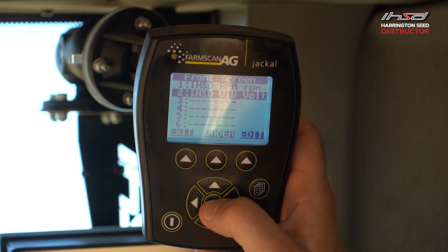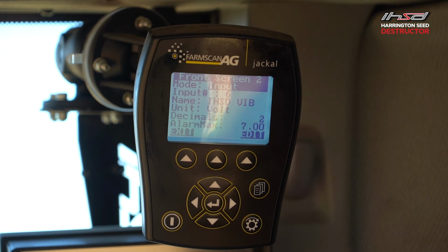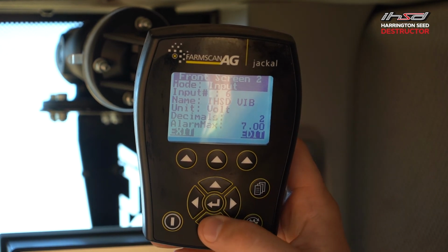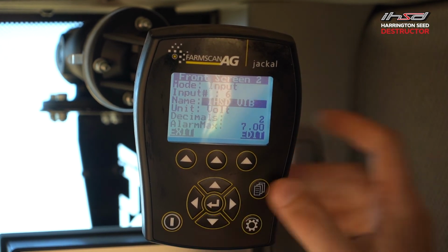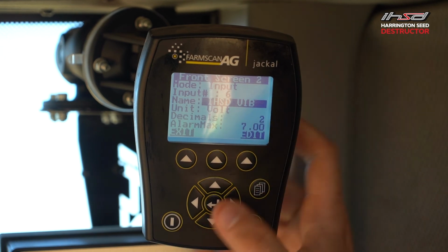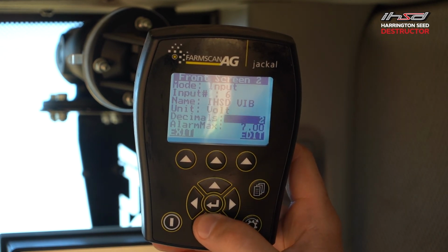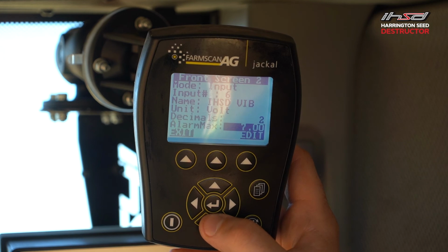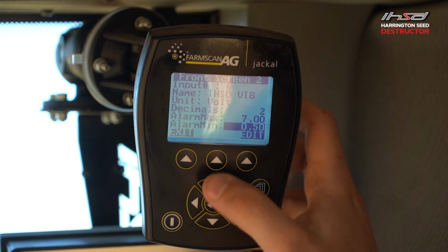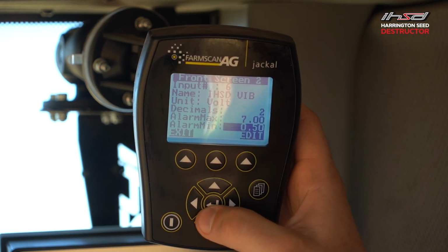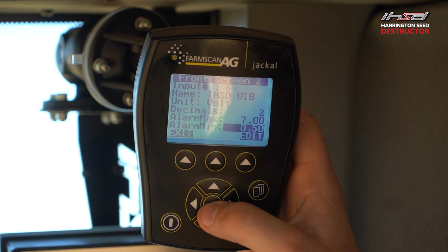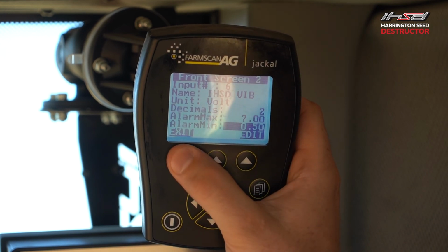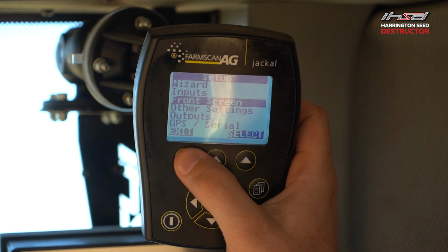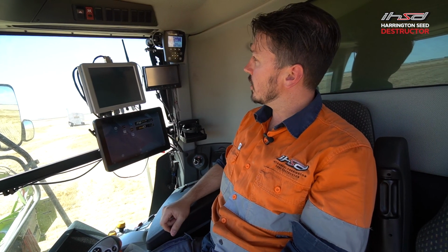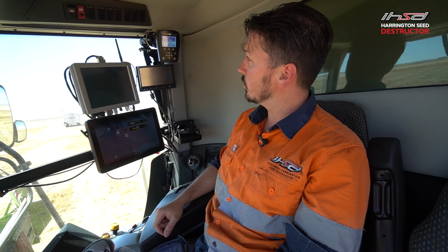Moving on to the vibration sensor. Again, mode should be input. Input should be number 6. Again, we just call it iHSD vibe, and the unit should be volt. Again, decimals 2. Alarm should be set at 7, and then the alarm min should be set at approximately anywhere from 0.5 to 0.9. And that covers the general output of the Jackal.